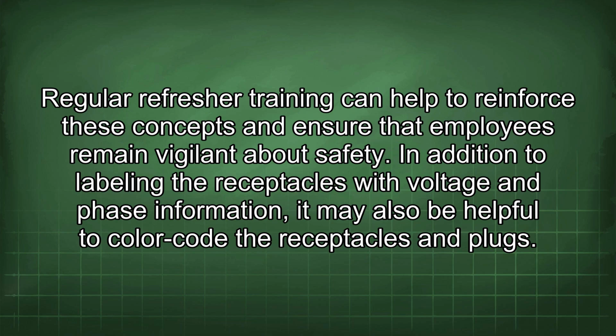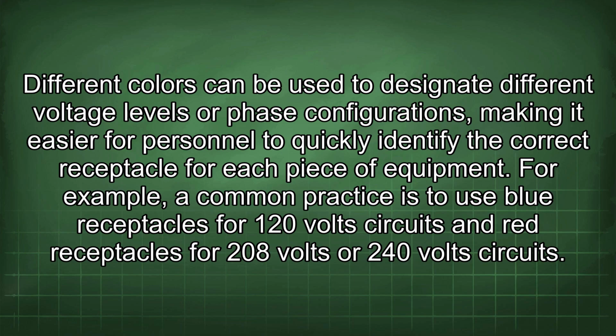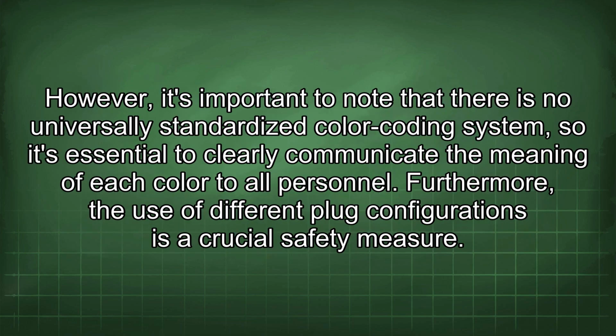In addition to labeling the receptacles with voltage and phase information, it may also be helpful to color code the receptacles and plugs. Different colors can be used to designate different voltage levels or phase configurations, making it easier for personnel to quickly identify the correct receptacle for each piece of equipment. For example, a common practice is to use blue receptacles for 120-volt circuits and red receptacles for 208-volt or 240-volt circuits. However, it's important to note that there is no universally standardized color coding system, so it's essential to clearly communicate the meaning of each color to all personnel.